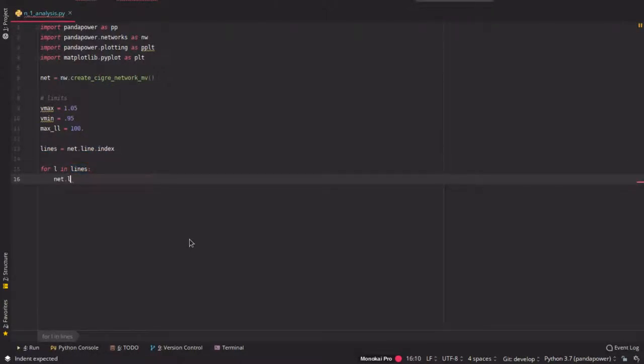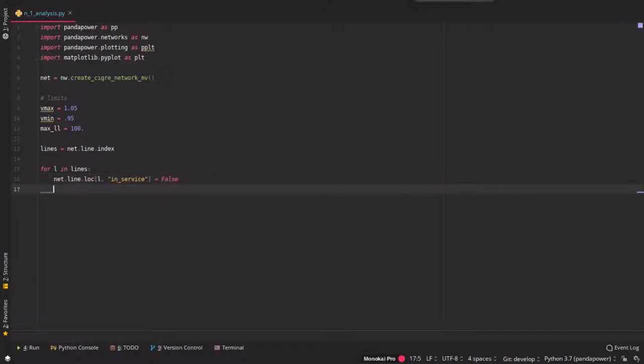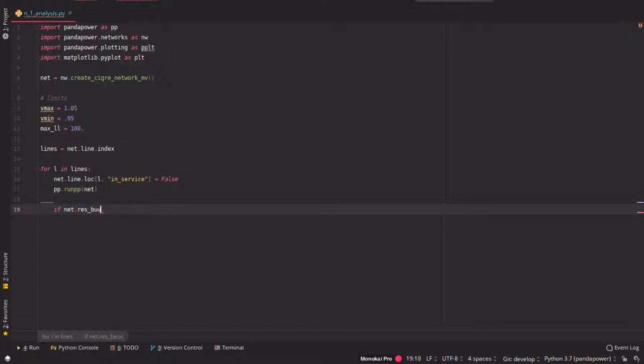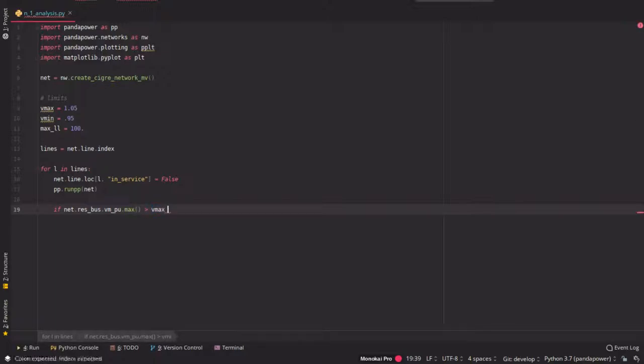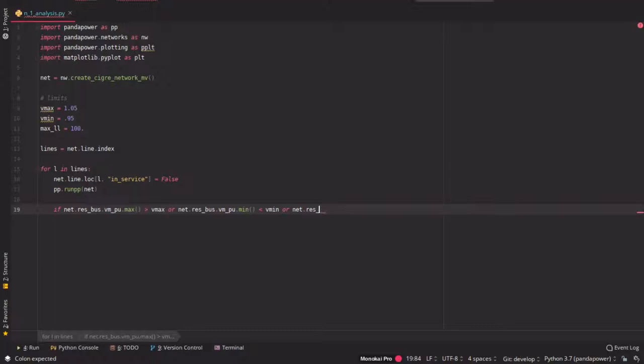And now we just iterate over each line here in the grid and we take a line out one by one by saying that the in-service status of line is false. Then we do a simple power flow calculation and now we can check if the res_bus value, so the per unit value of the bus, the maximum value is greater than Vmax or we do the same practically for Vmin. So we check for the minimum of the voltage limit and also for the lines.